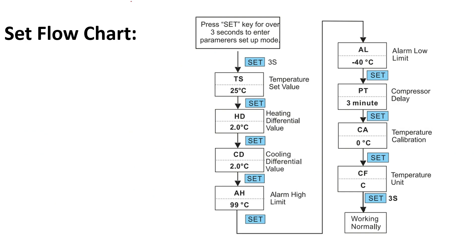To set the temperatures and different menu codes, the user has to press the SET key for three seconds to enter setup mode. The first parameter is the temperature set value, which is set using the increase and decrease buttons. After that, press the SET key to move to the heating differential value, which then needs to be set.